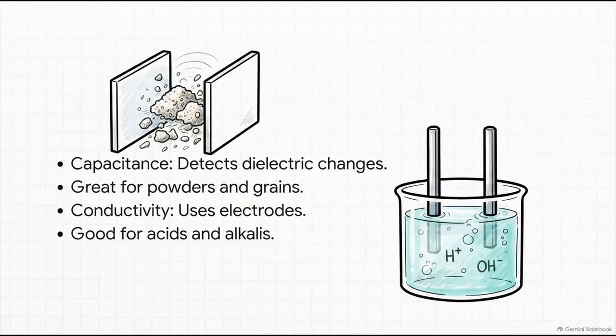Capacitance transmitters detect changes based on the material's dielectric constant as it covers a probe. The best part? Zero moving parts. That makes them fantastic for granular solids that would easily jam up a mechanical float. Conductivity transmitters, on the other hand, use the actual electrical conductivity of the liquid itself. When a conductive liquid, like an acid, touches the probe, it completes the circuit between electrodes, giving you an instant, rock-solid reading of the level.